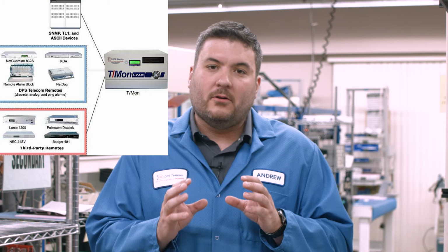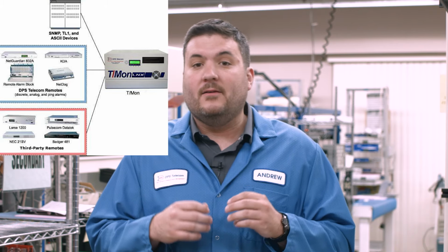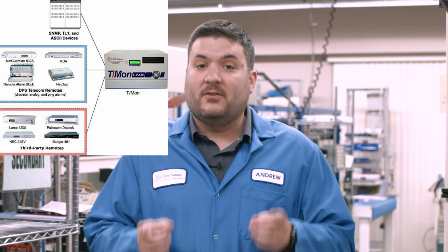It's really important that you collect everything and have it up on one screen, or you can have your central alarm master server sending out messages as emails, as text messages. You need to have that complete picture. You never want to have one master station for 40% of the remote sites, and there's some other equipment out at some of the other ones, and that's going to be Modbus, and you have your head on a swivel, you're looking around, people get confused, it's hard to train, a lot of problems. You want to bring that all into one master station. So that's absolutely critical. Don't think that you need to have a different system for each protocol. You can have a single multi-protocol master station.